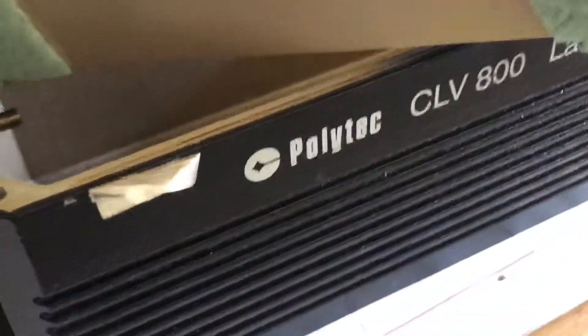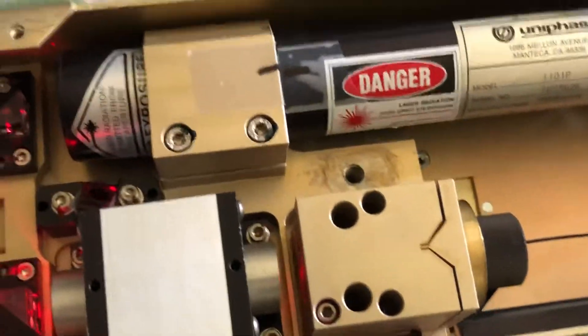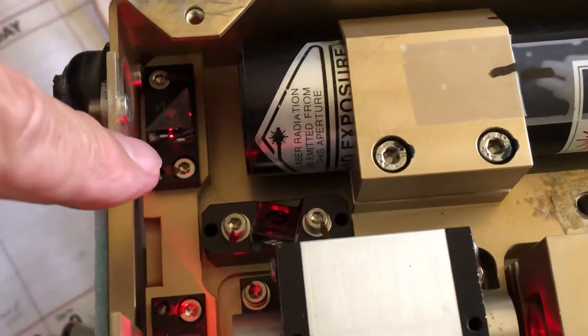What we have here is a Polytec CLV 800 laser Doppler vibrometer. You can see the laser output is here, goes through a prism, a beam splitting prism here.